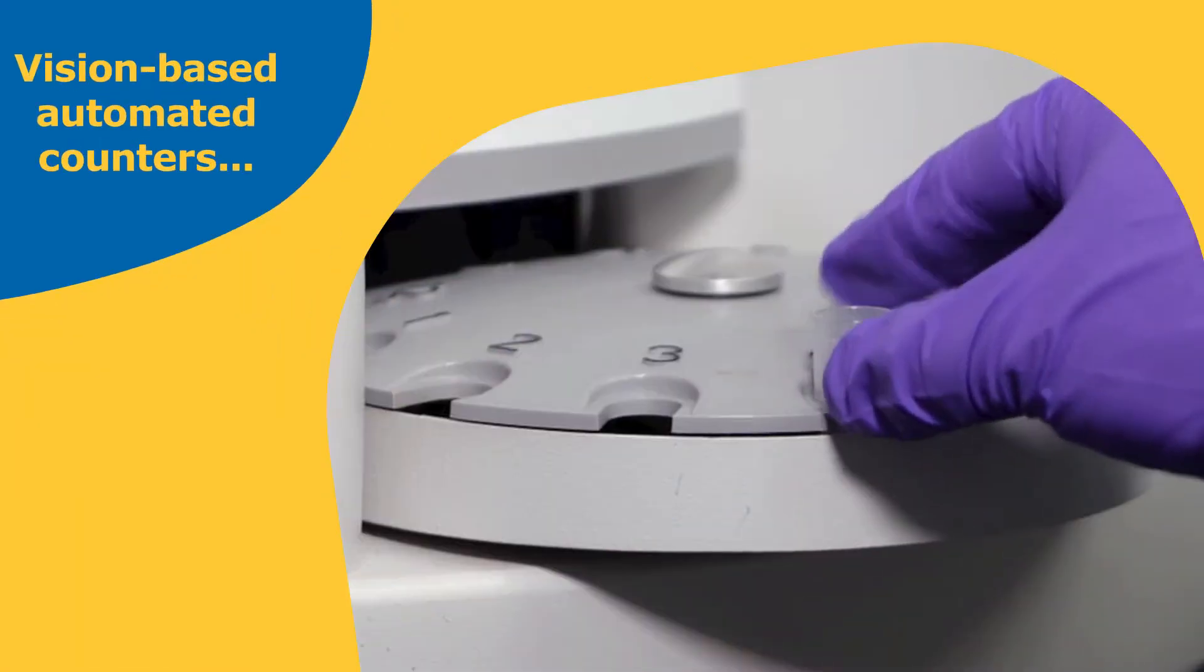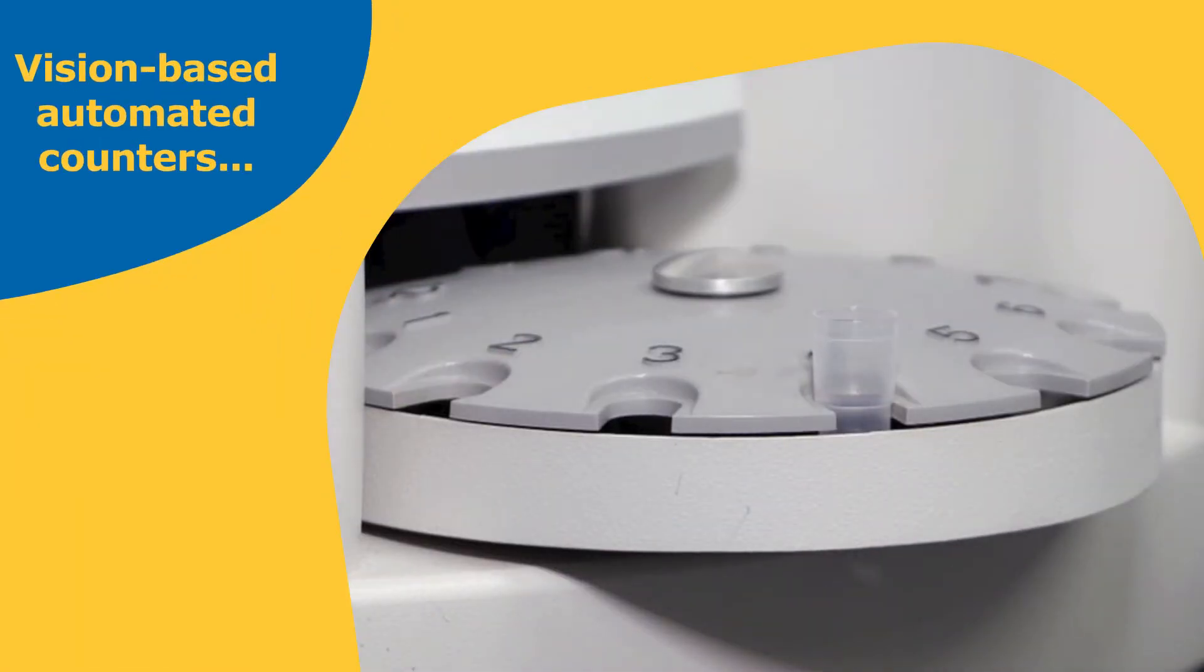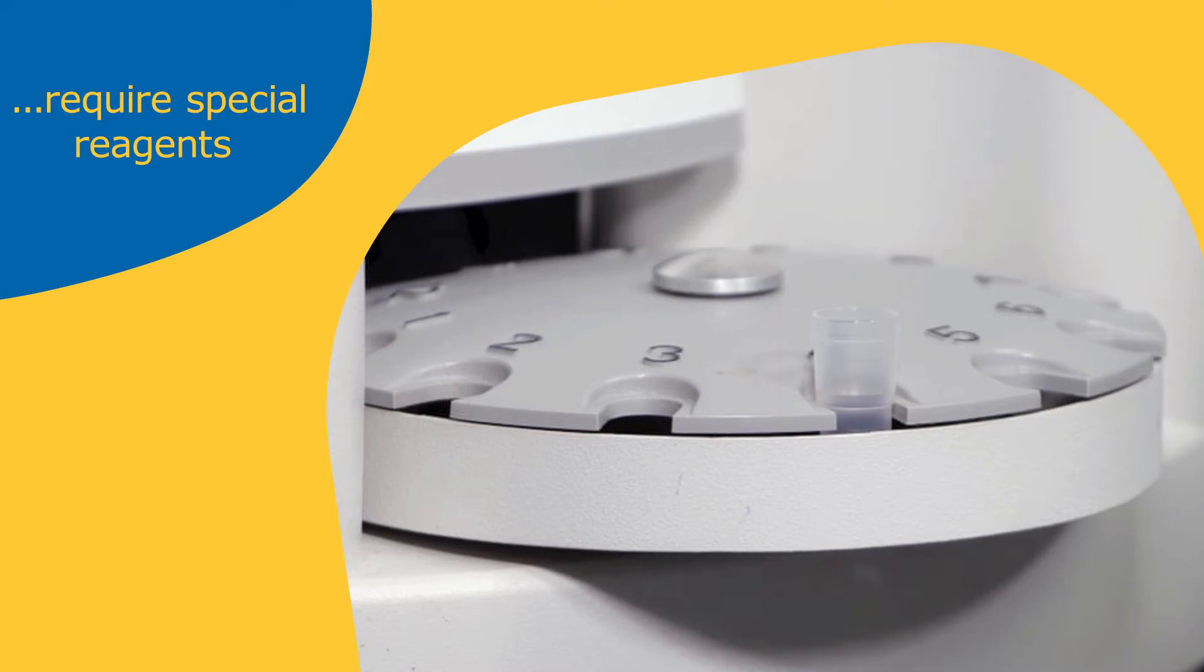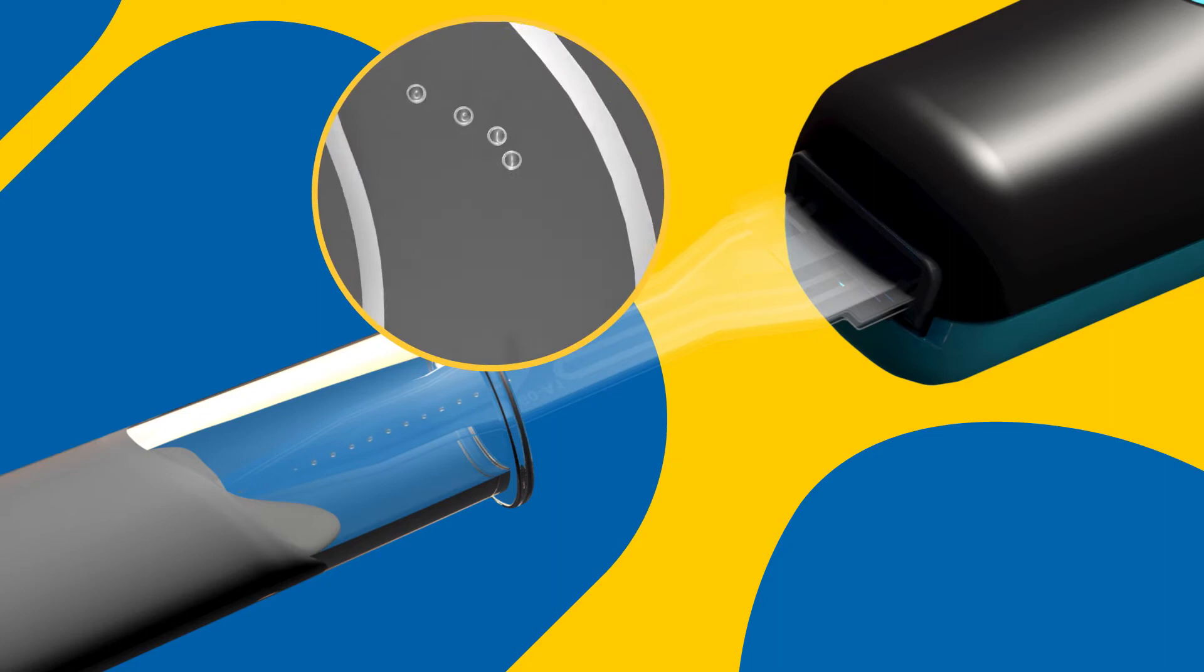Obtaining counts is as easy as pipetting—simply insert the sensor into the sample and draw the sample into the instrument. Unlike vision-based automated counters, no special and potentially toxic reagents are required. Cells are counted as they pass in a single stream through microfluidic channels in the sensor.